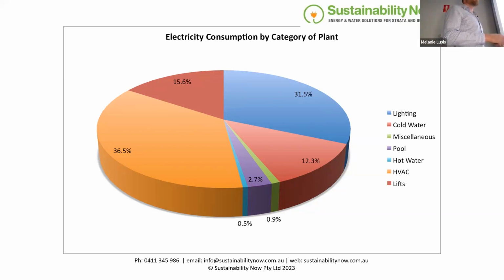Cold water pumping - in this case they had a header tank where they pumped with a jacking pump, pumping water up, and then it's gravity fed down to the lower floors. But because the head's not quite enough, they have to actually pump for the first few floors as well, so they have pressure pumps up the top. So they're pumping it from the ground up to fill a tank, then pressurizing it again up top to do the first few floors, and then it's gravity fed from there down. So yeah, there's a lot of pumping of water in high rise buildings.